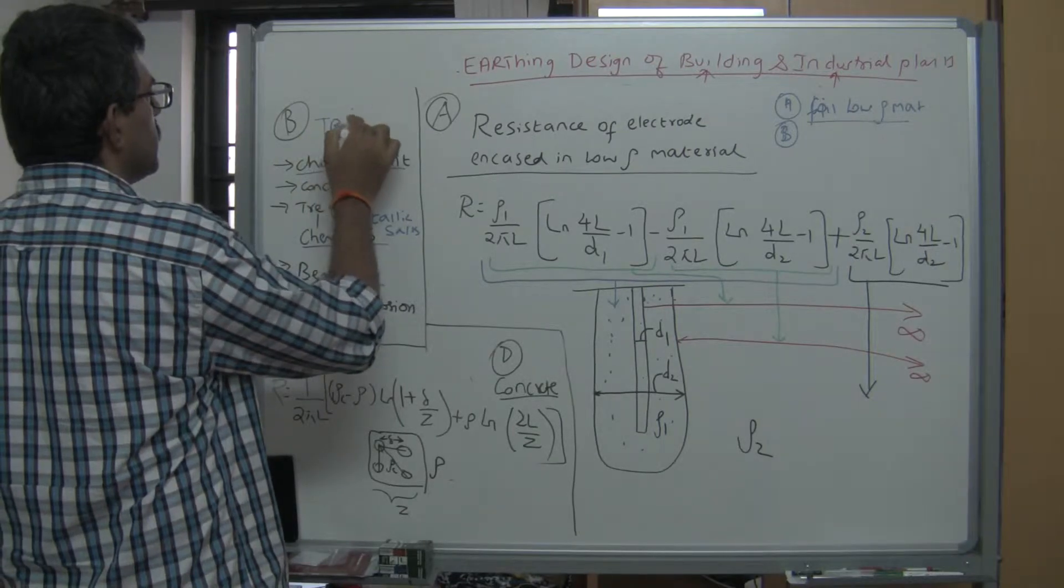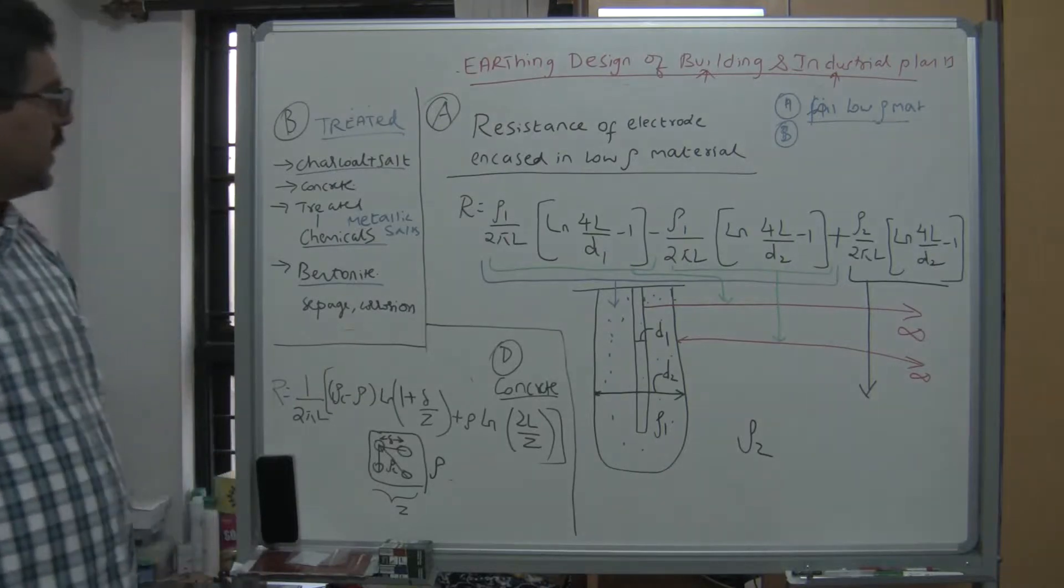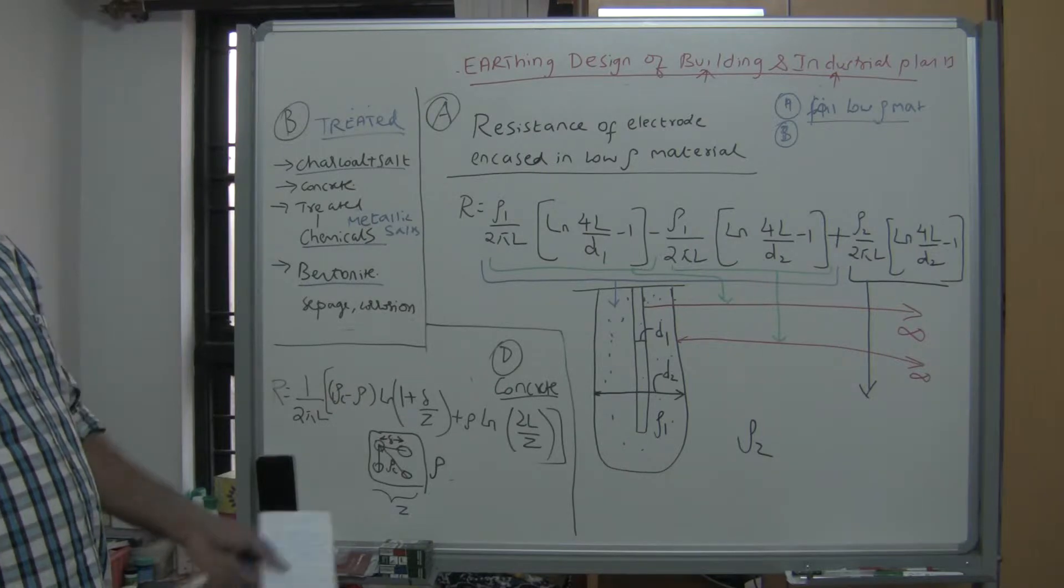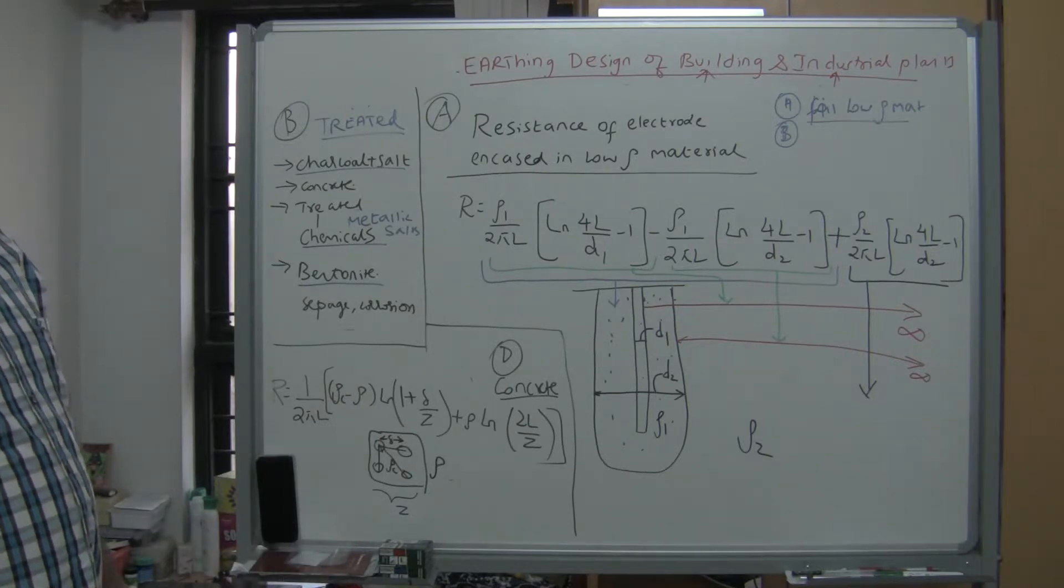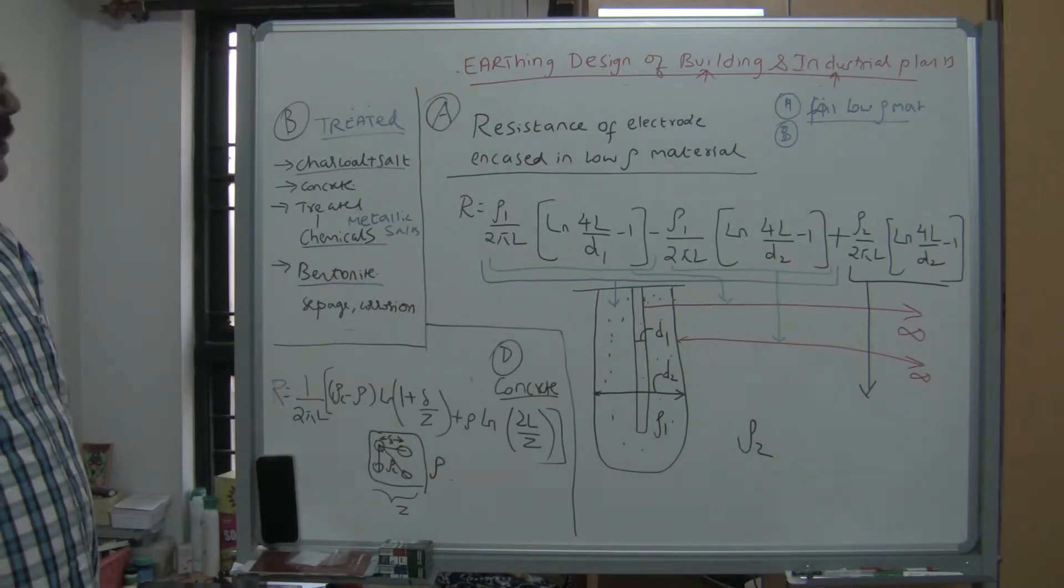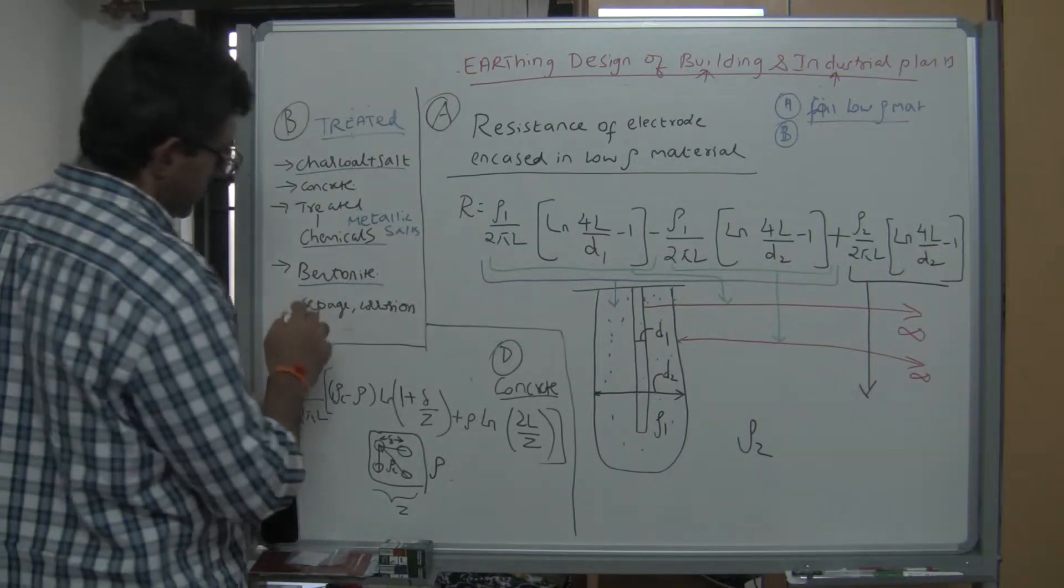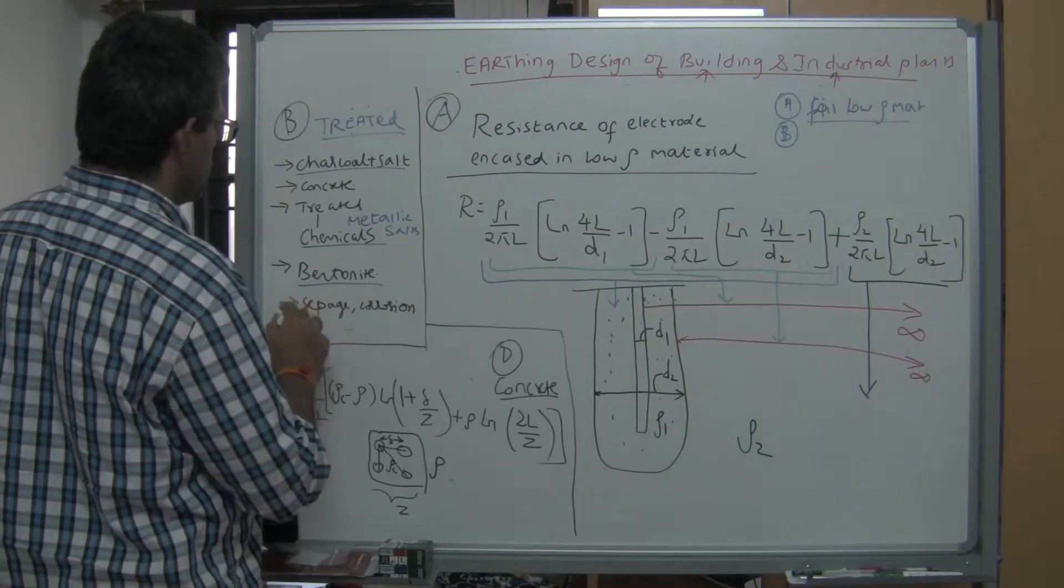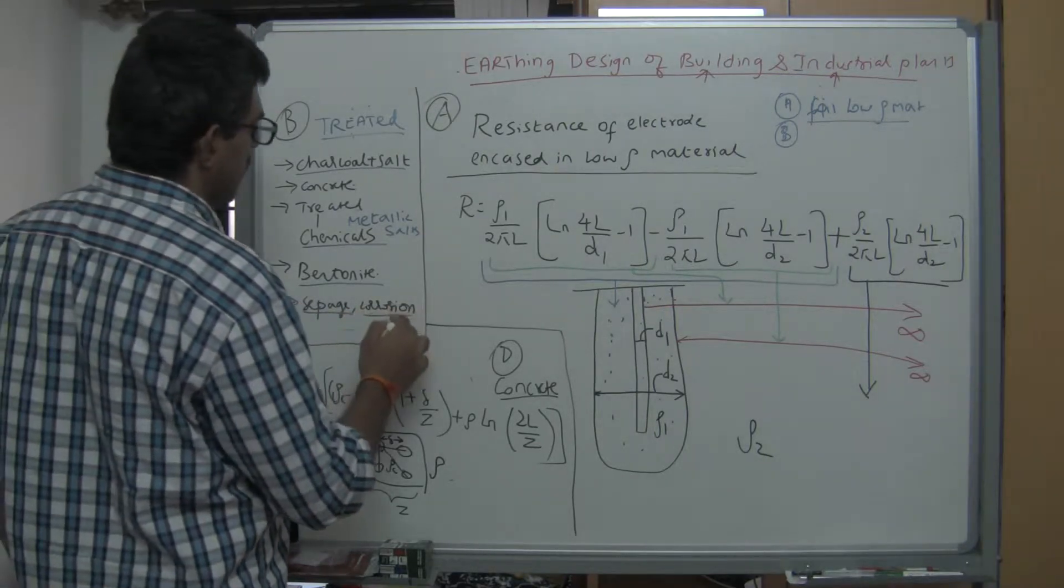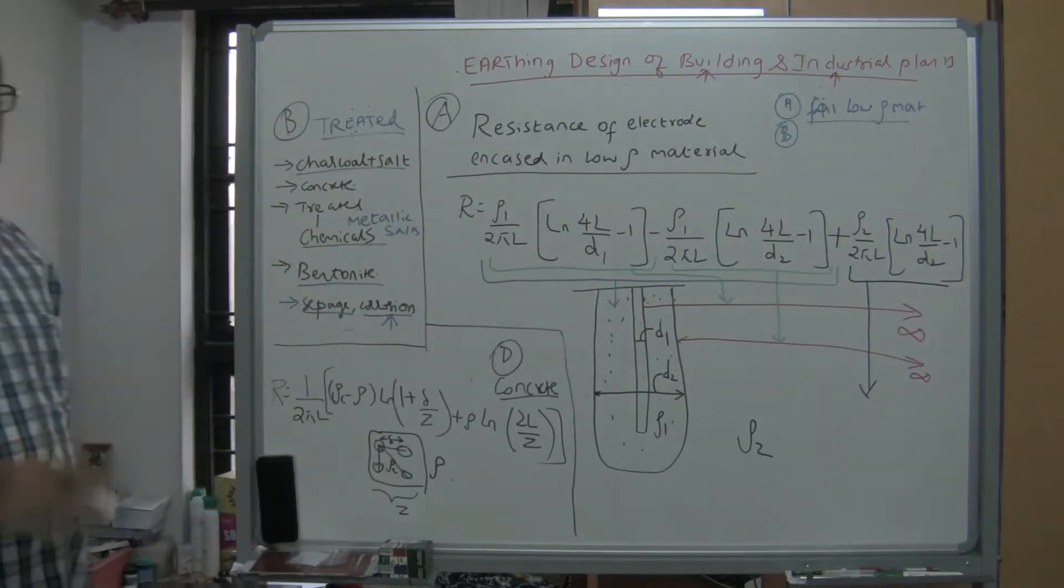This treated earth pit has an advantage - you get low resistance when an area has very high resistivity. However, there are also disadvantages: it may lead to seepage, the groundwater may get contaminated, and it may accelerate corrosion. So before you use a treated earth pit, please check whether local regulations allow it.